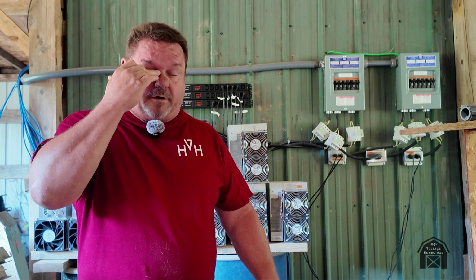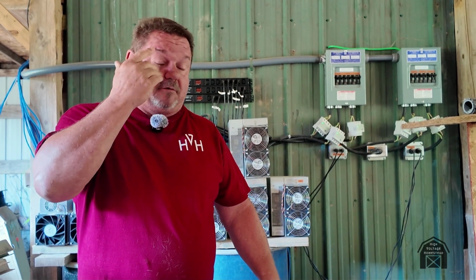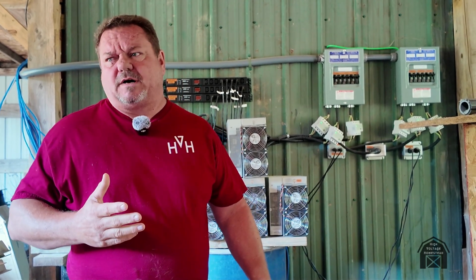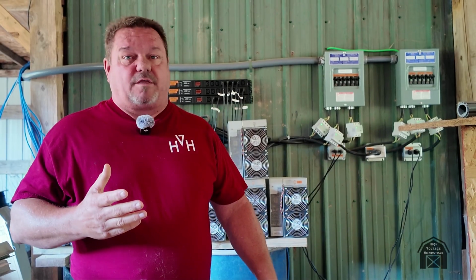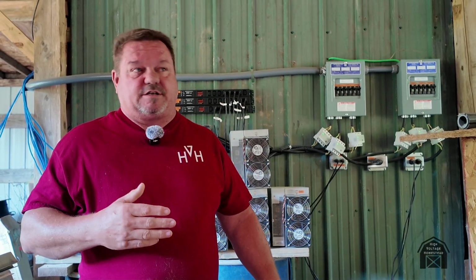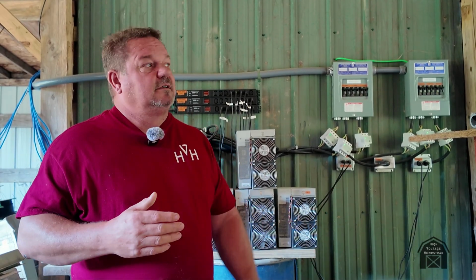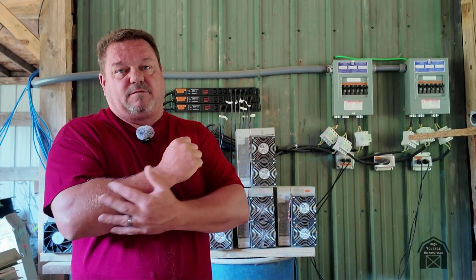130 is not where you want your boiler. Your boiler should run about 180, 185. But at 130, it will still work, it just runs a little bit longer. But if your heated water is free at that point, then it really doesn't matter if it runs an extra 15 minutes in the cycle. But that was the third reason I went with water cooled.